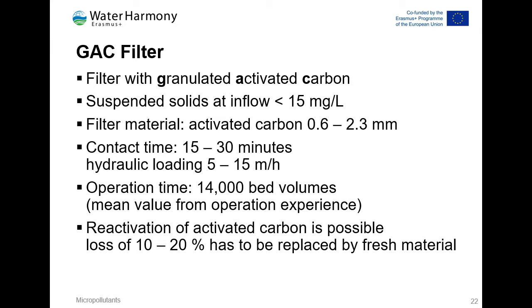And of course, after a few years it's loaded and you have to remove this. And the other application, so the solid concentration has to be very low, and the contact time is also something about 15 to 30 minutes. And experience at the moment, from the first applications, is that we have a use of the activated carbon for approximately 15,000 bed volume. You can reactivate the carbon, but it's very expensive, and you have to replace this partly by fresh material.